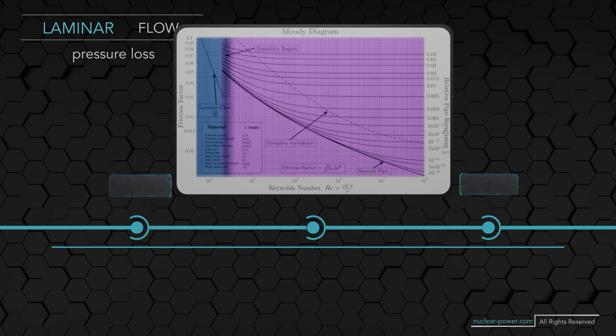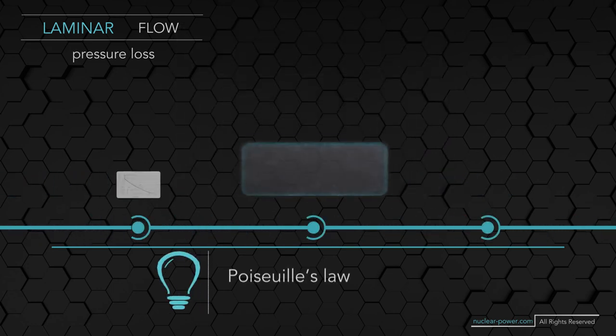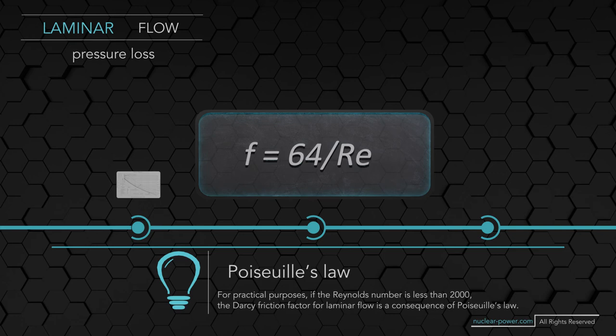For transition region and especially for turbulent region, we have to select the curve corresponding to the relative roughness of the pipe, and then we get the friction factor for the given Reynolds number. As can be seen from the Moody diagram, the pressure loss for laminar flow is proportional to velocity rather than velocity squared. Thus the friction factor is inversely proportional to velocity. For practical purposes, if the Reynolds number is less than 2000, the Darcy friction factor for laminar flow is a consequence of Poiseuille's law. For circular pipes, the friction factor can be directly calculated. For non-circular pipes, it depends on the cross-section of the pipe.